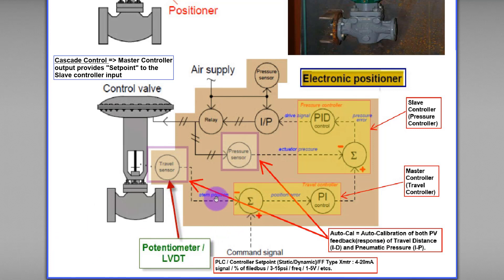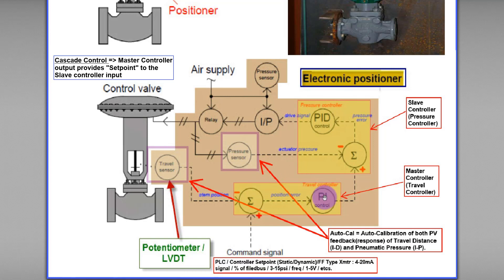The other input is the process variable — feedback from field instruments. The difference between the set point (command signal) and the process variable feedback from the sensor in the field will produce a position error to the PI controller of the master controller. PI stands for Proportional-Integral controller.